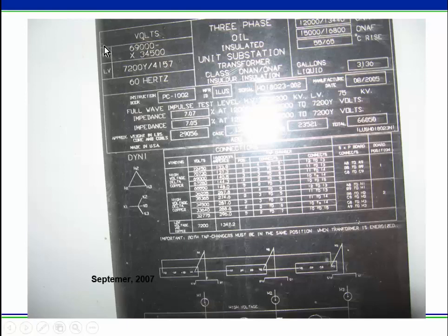So if we put them in series, what voltage do you think we would be? And if we are in parallel, which voltage would it be? I think you know the answer to that, I hope. Notice the class. The class is how it's cooled. O means oil, N means natural, A means air, F means forced. So oil natural, air natural, oil natural, air forced. So these are two different ways you can go. Essentially, the oil will circulate through the radiators naturally, and air would convect over the radiators naturally, or you can turn the fans on in this case and get some forced air. And these ratings then correspond to that.